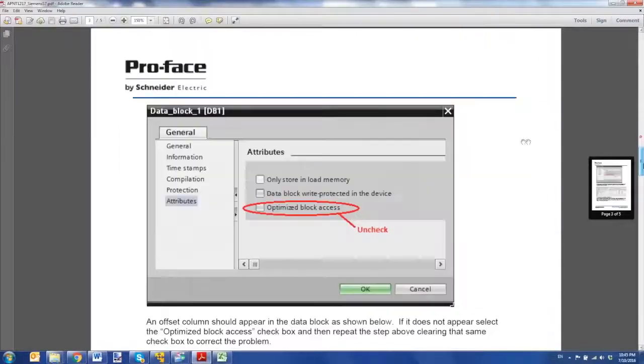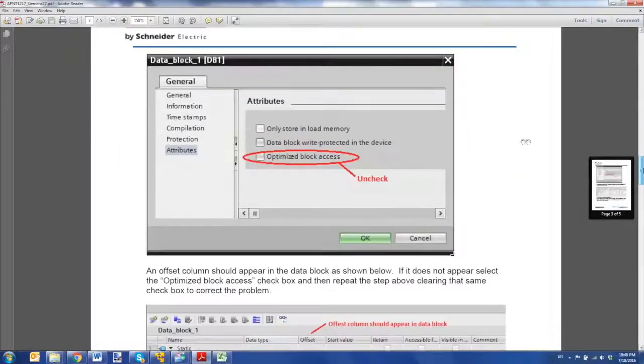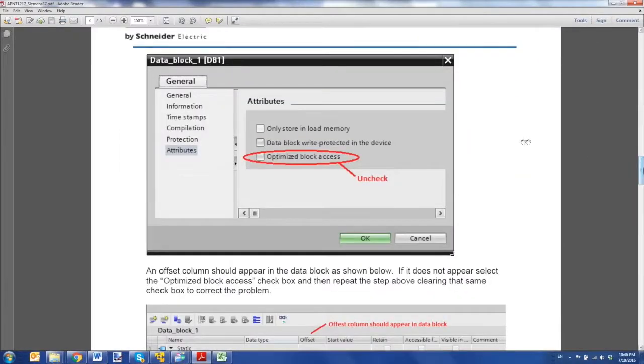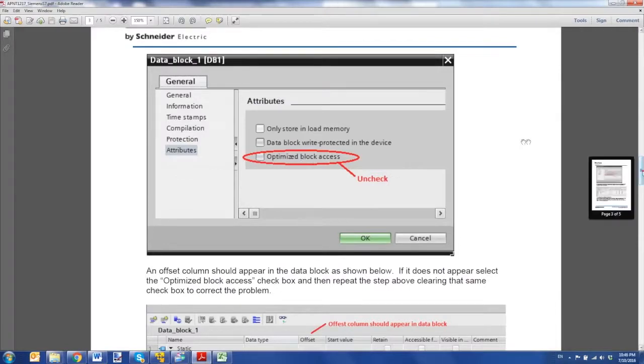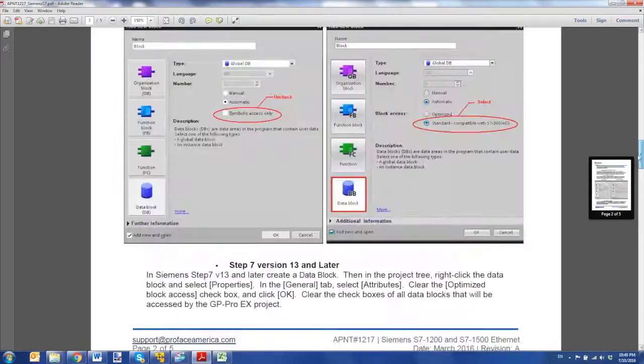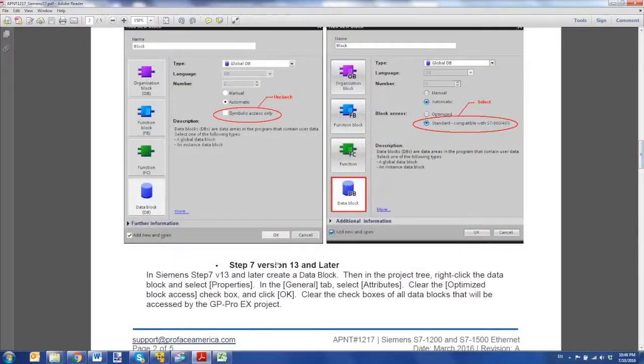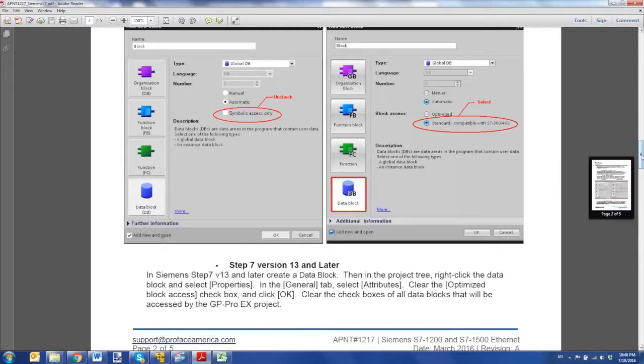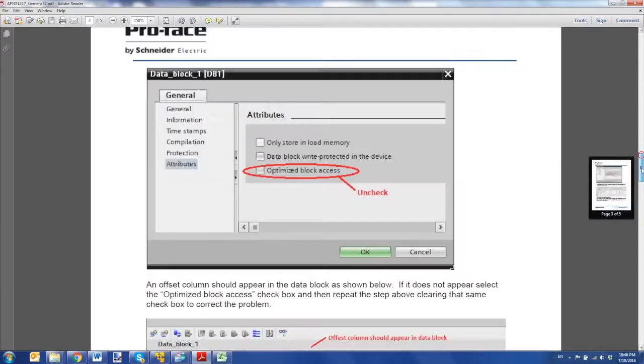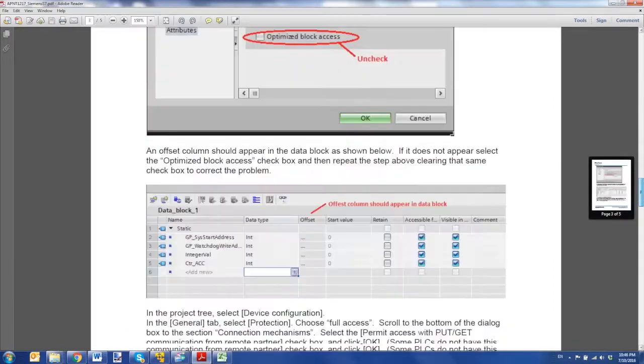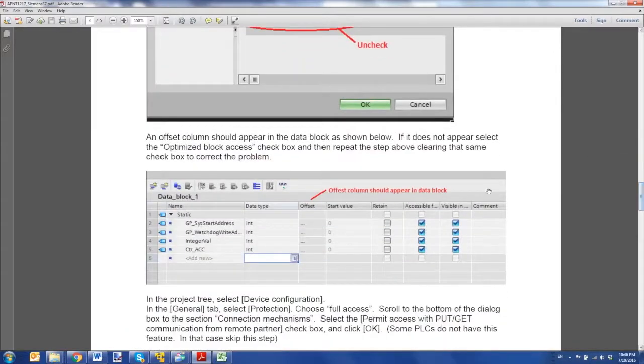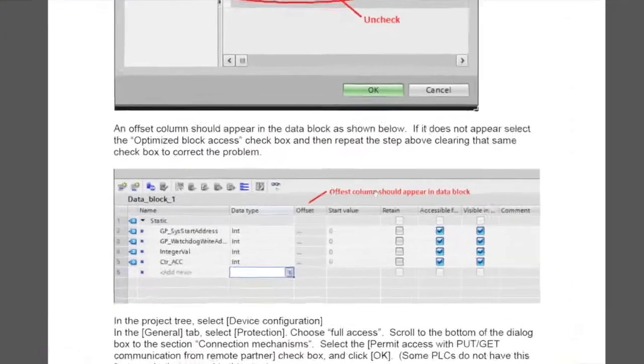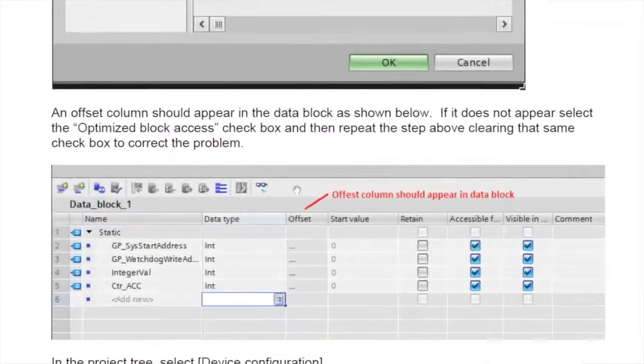Next, you're going to want to uncheck the optimized block access on the data blocks themselves, and that applies for step 7 version 13 and later. Also, you want to see this offset column in the data block.